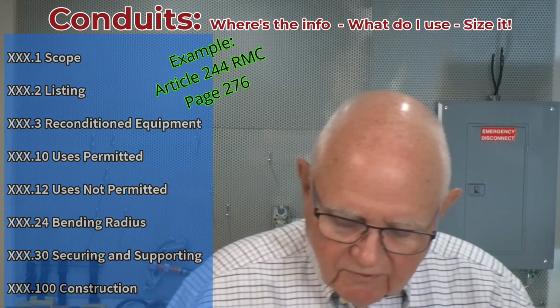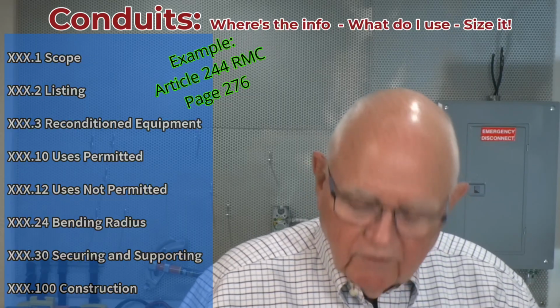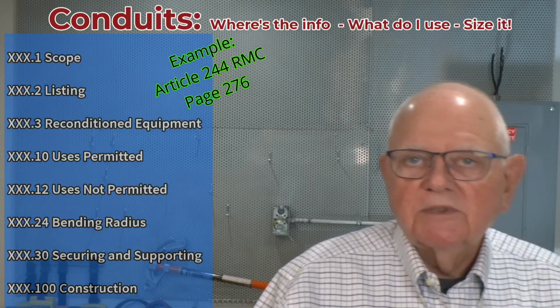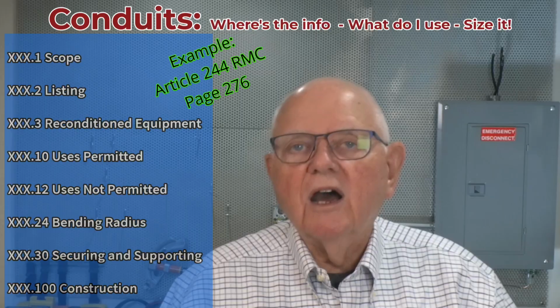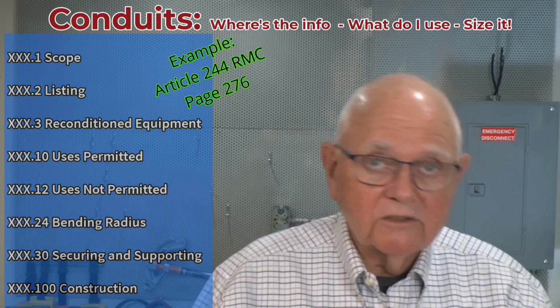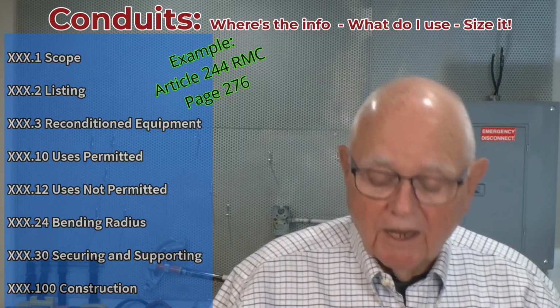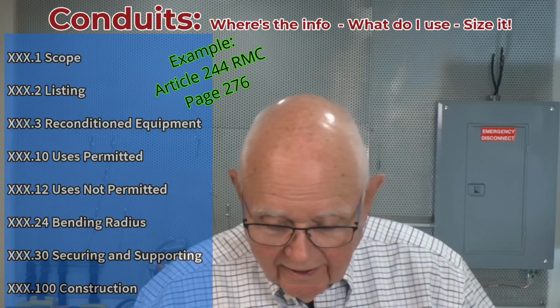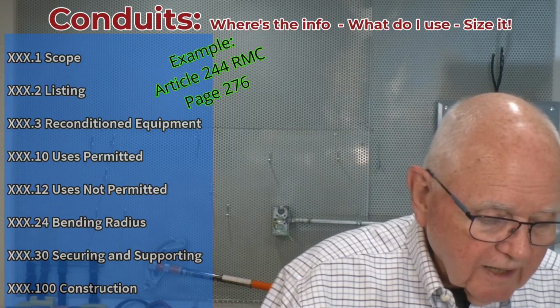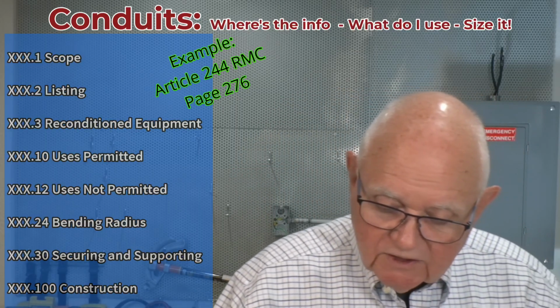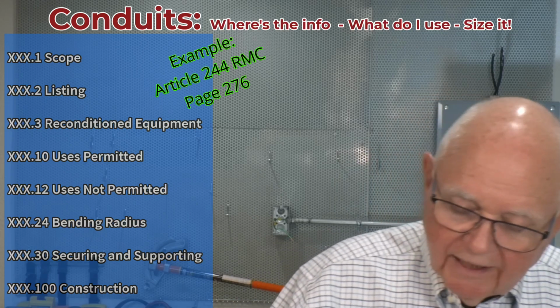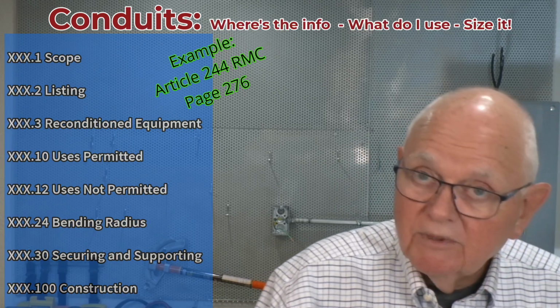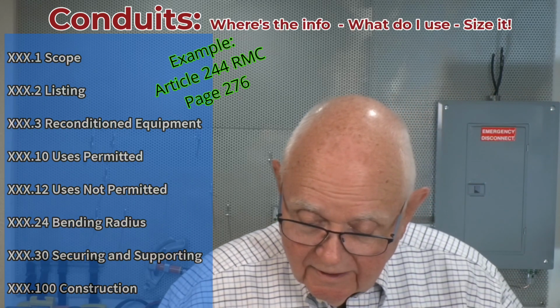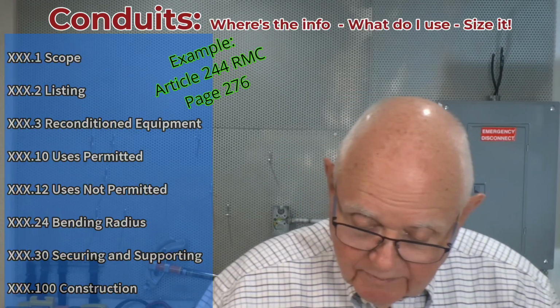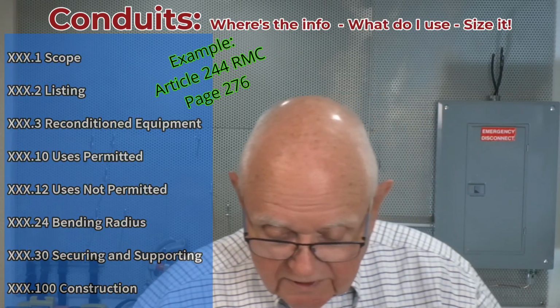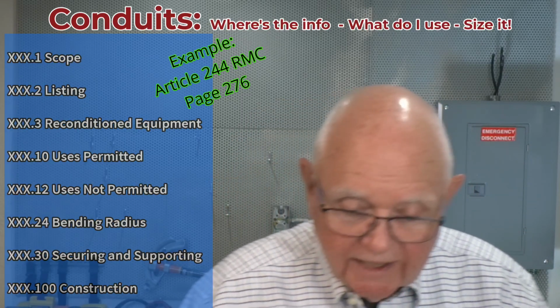Now, Part 3 then, 344.60 tells me that I can use my rigid metal conduit for my equipment grounding conductor. Obviously, that's going to depend on the type of conduit as well. And then 344.100 is my construction requirements, pretty simple, and tells me what I've already been talking about, what types of materials it can be: steel with protective coatings, aluminum, red brass, or stainless steel.